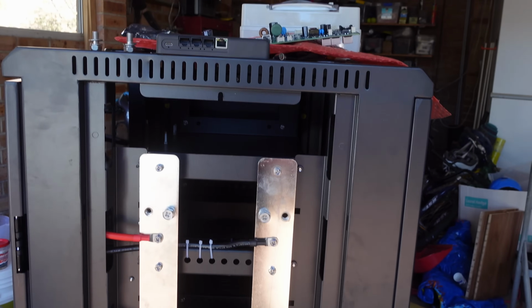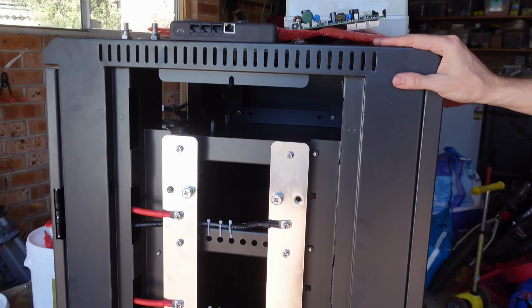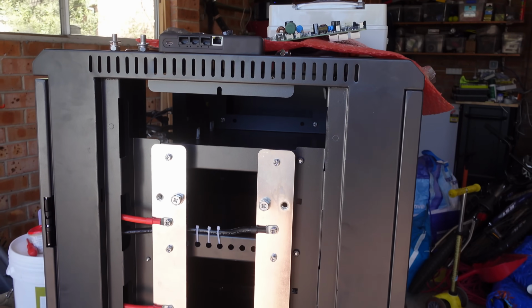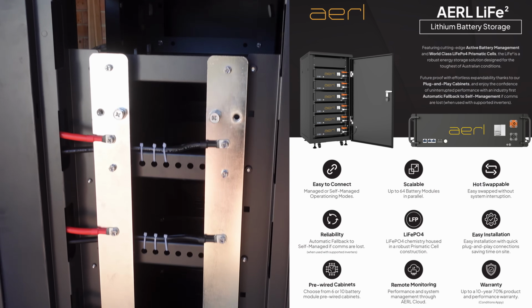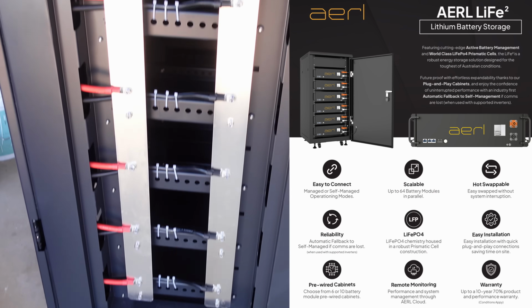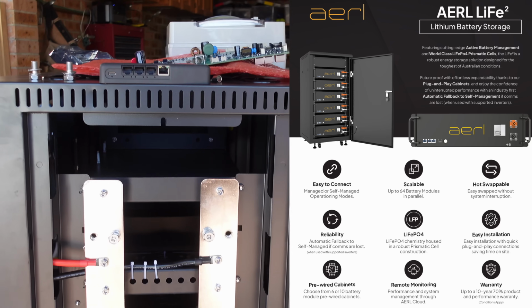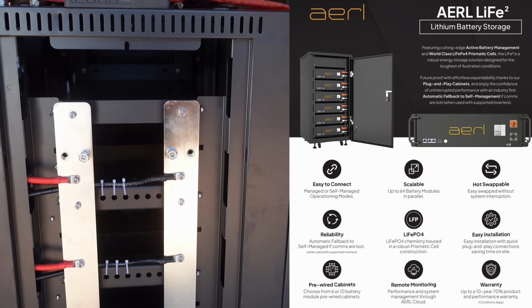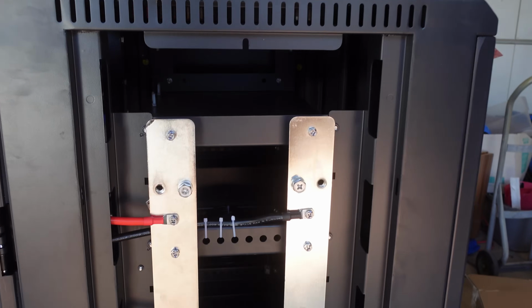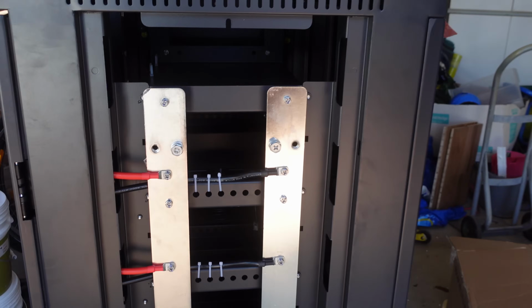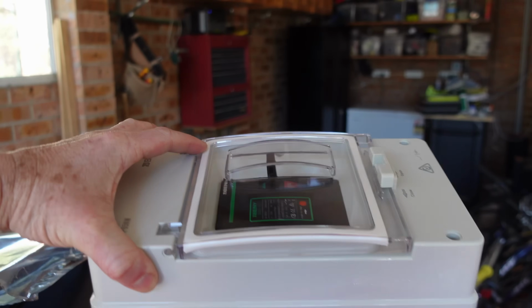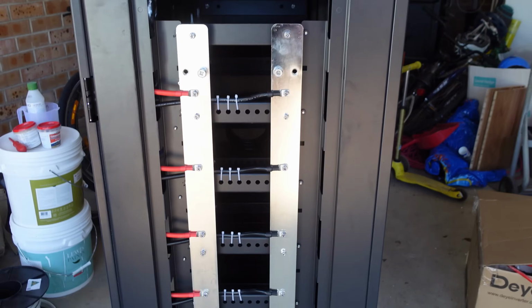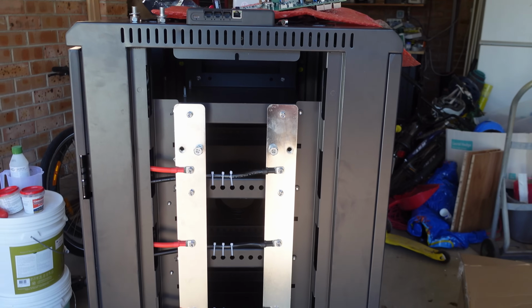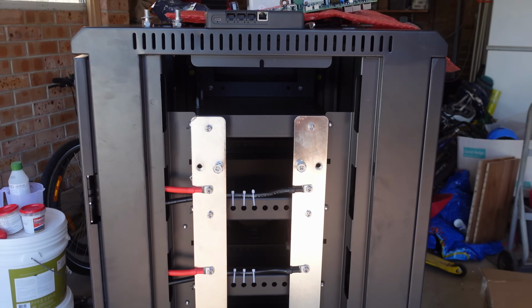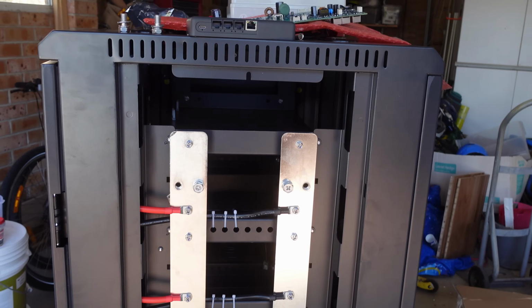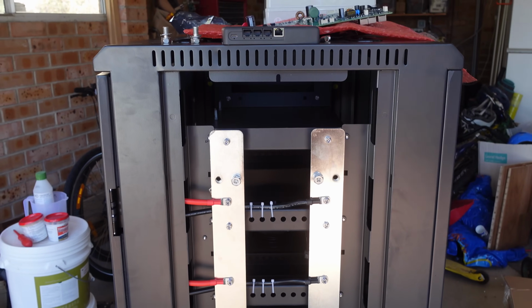Let's talk about this rack briefly. What have we got here? This is our 6-way pre-wired battery cabinet for the Life Squared. We have everything in here you need to just slot the modules in and plug and play. We've got our 600 amp DC bus, 100 amp per battery, that you effectively just connect through to, joining in today via a giant breaker - our DC 2-pole circuit breaker that'll be between this cabinet and the Deye inverter. The only other thing we need to run is a Cat6 comms cable between the batteries and the inverter, and the inverter will self-detect the batteries - that's kind of it.